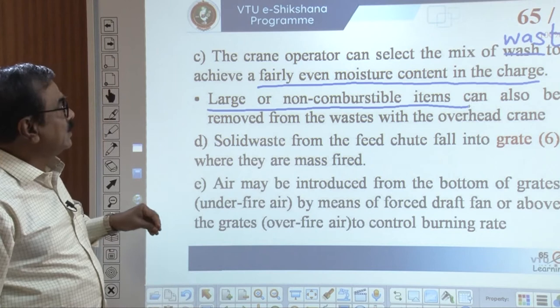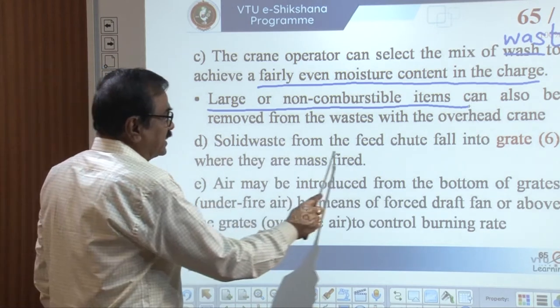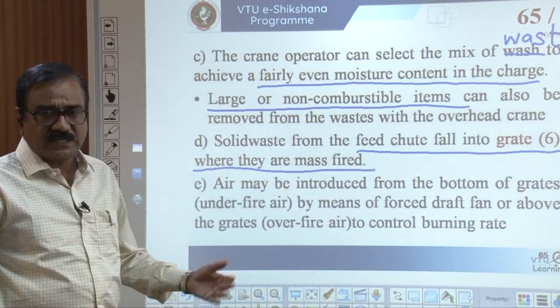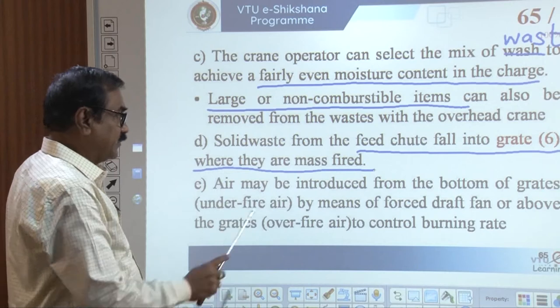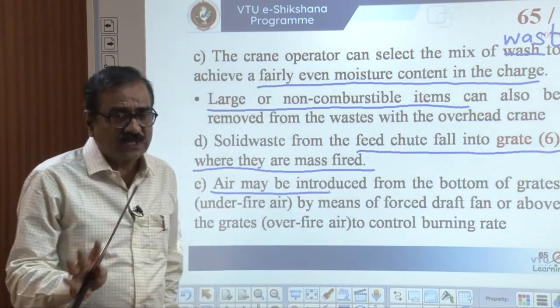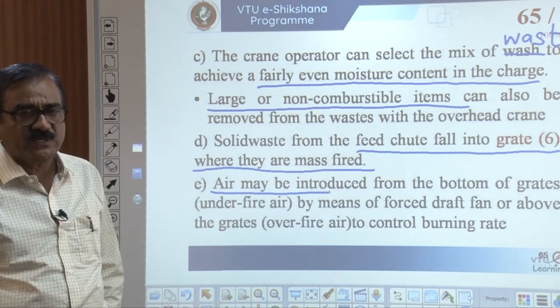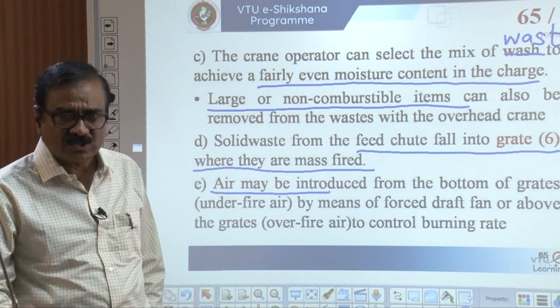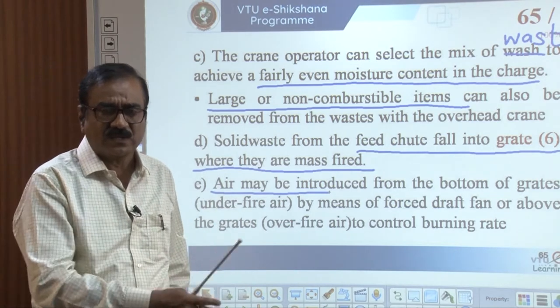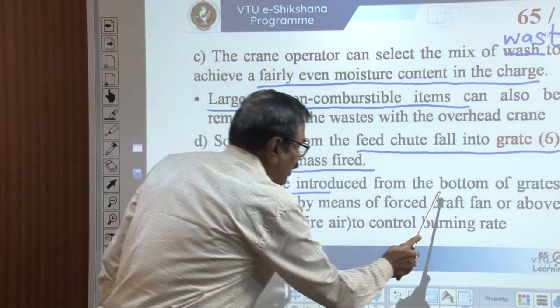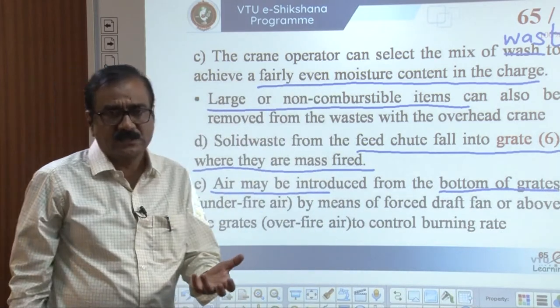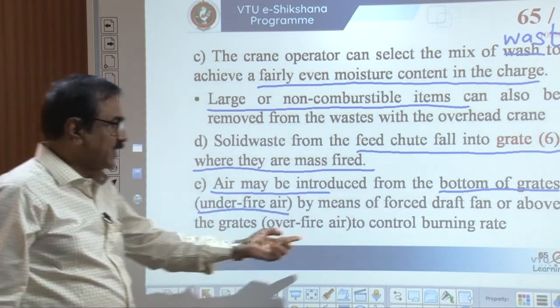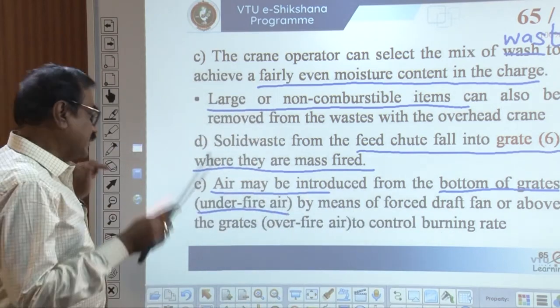The solid waste from the feed chute falls onto the grates — the furnace — where they are mass fired. Burning of solid waste requires air; it is a combustion process. The difference between combustion and incineration is that in incineration, slightly excess stoichiometric air or oxygen is required. Air is introduced from the bottom of the grates, which is known as under-fire air, by means of a forced draft fan.